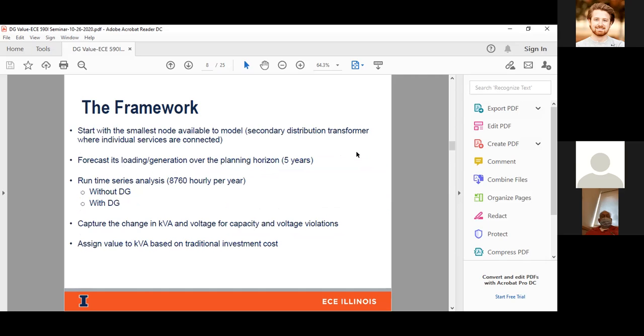So overall, how did we actually operationalize this and execute it? We took our distribution models for more than 2,600 feeders that we have in the Ameren Illinois territory, and we start with the smallest node available to us. Then we perform analysis with and without DG. You run your analysis as a normal case. If there's DG existing before your analysis, then you leave it in there. You use your typical forecast for that specific feeder, based on historical data as well as the data about load growth that you might put in there.